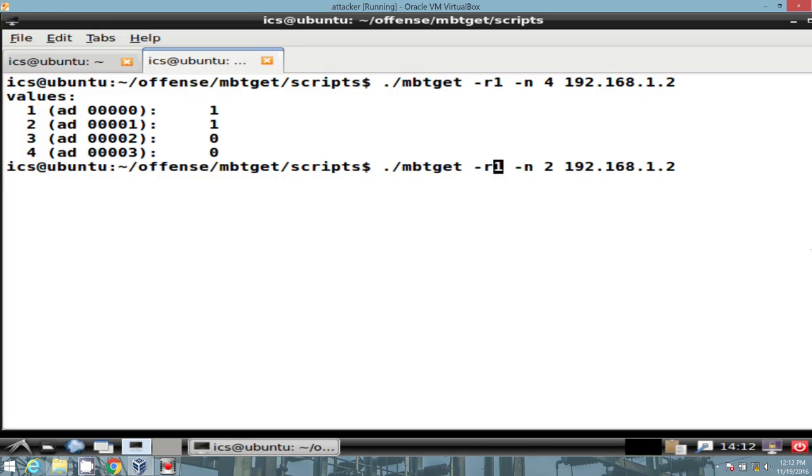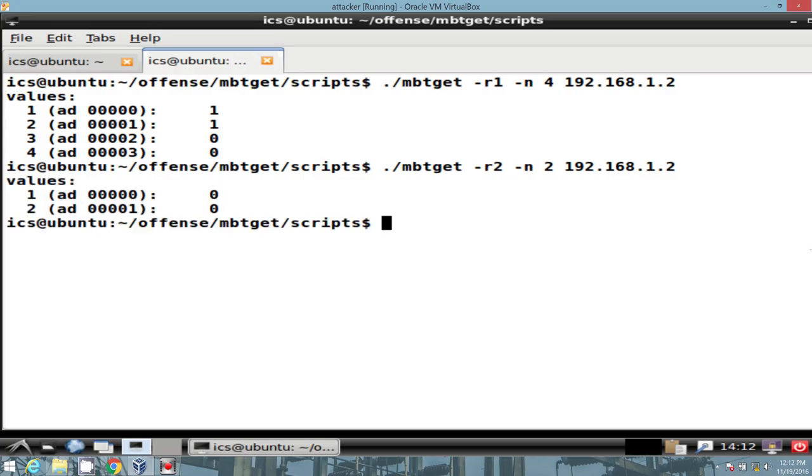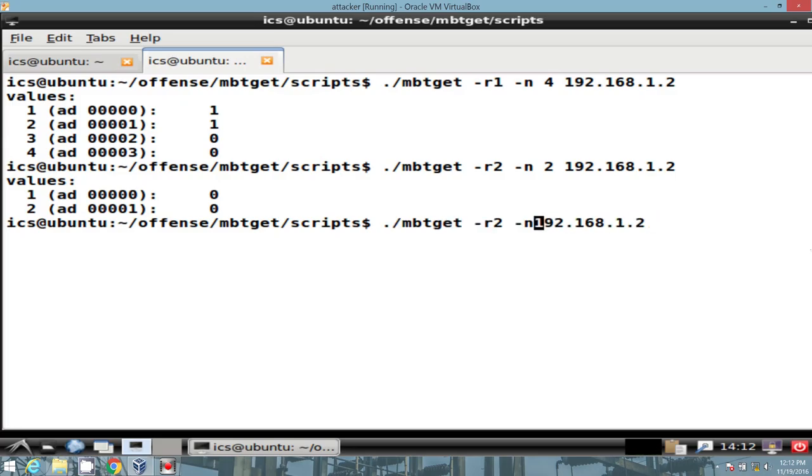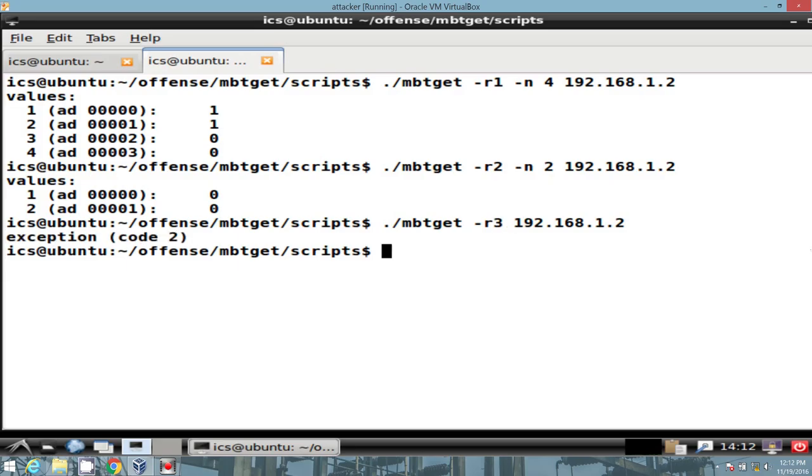We can change this to read input status, and we see we have nothing there. Additionally, if we would issue a function code 3, which is read holding registers, it fails with an exception code 2. And the reason why is because this particular model doesn't have registers.